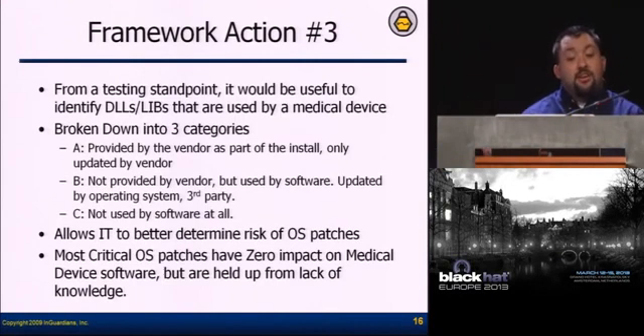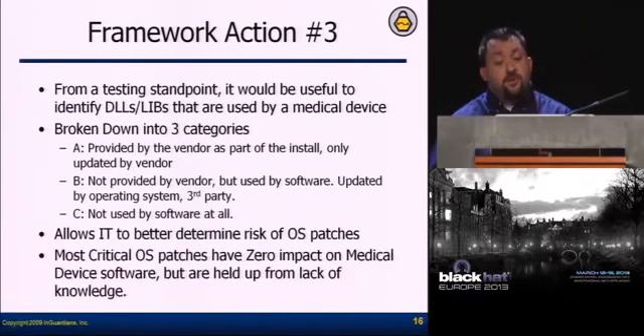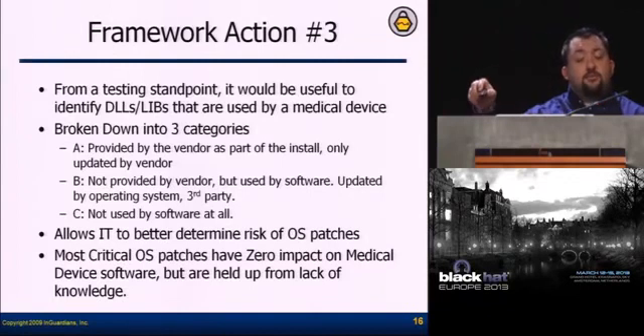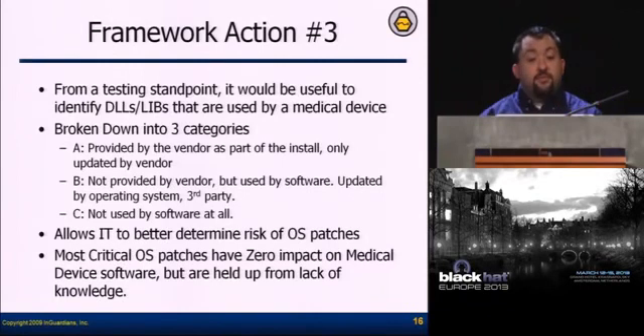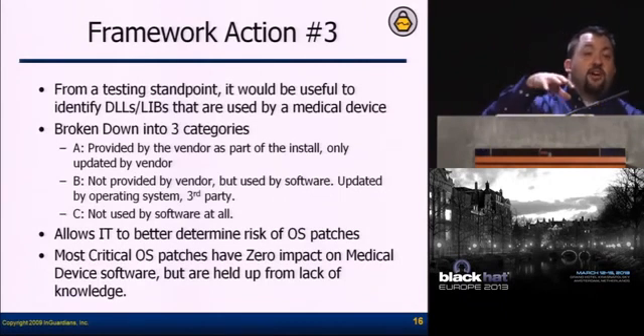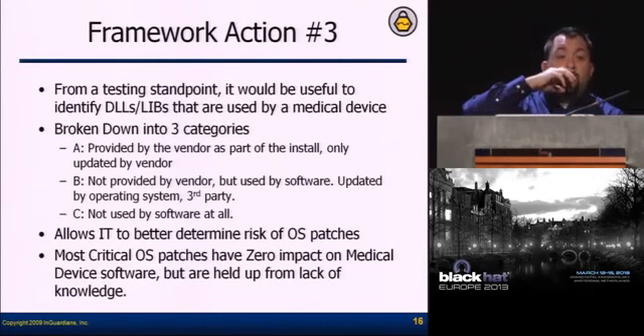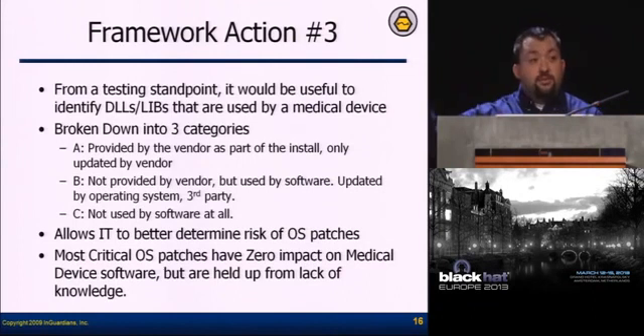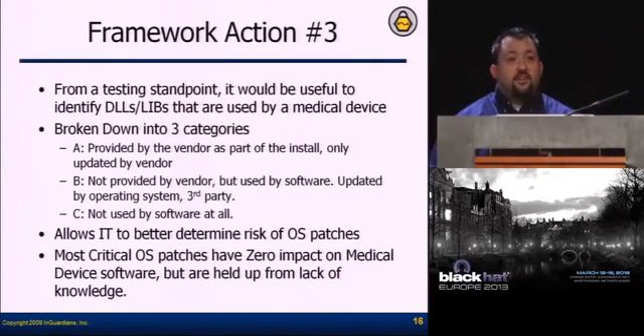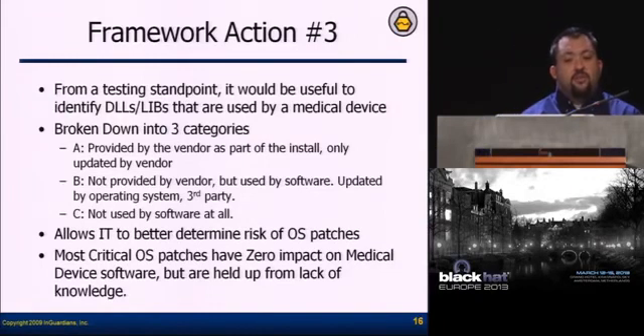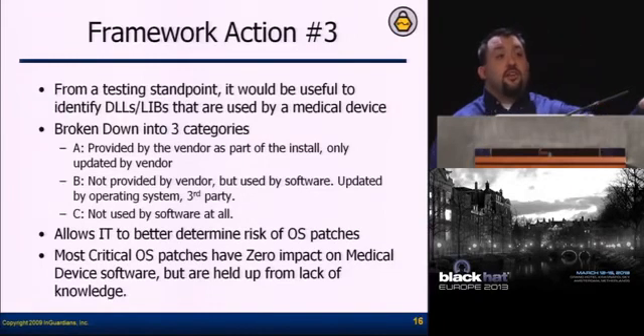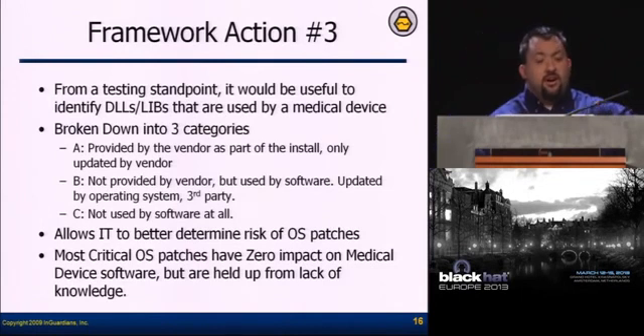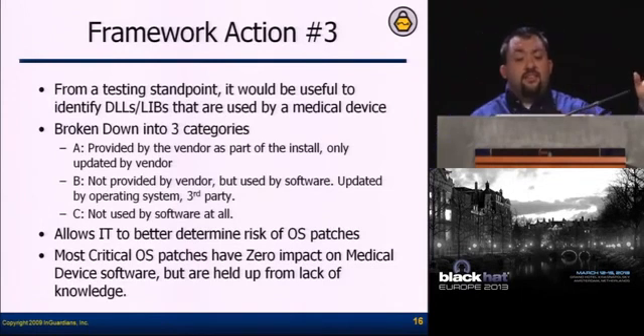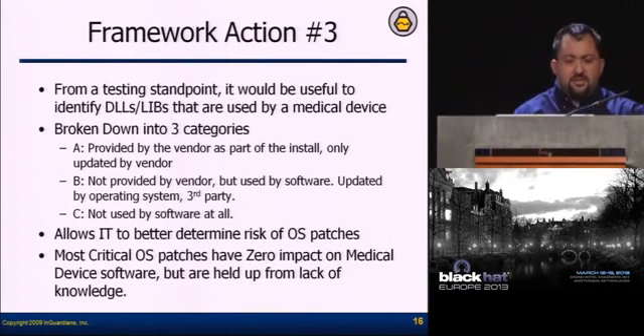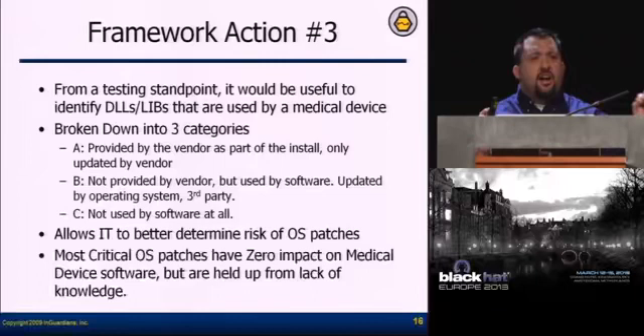Category B libraries would not be provided by the vendor, but are used by the software, right? That are updated by the commercial operating software, not by the third party. So your Acme's MRI software might need to use a library from Windows to be able to display menus, to be able to do all the things that generically are done inside the operating system. So the software is identified as using these libraries, they're important to it, and they use it. And Class C libraries would be everything else, right? The software doesn't use them, so they're not directly or indirectly touched by the software.